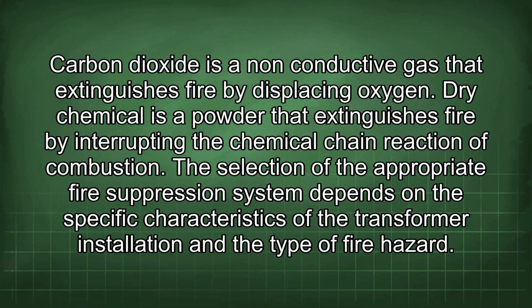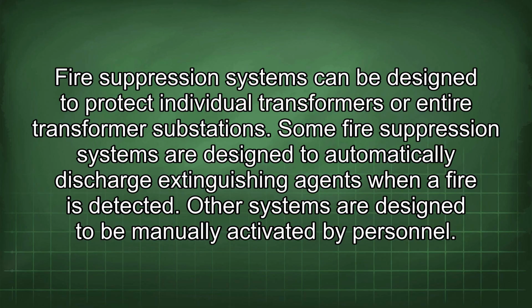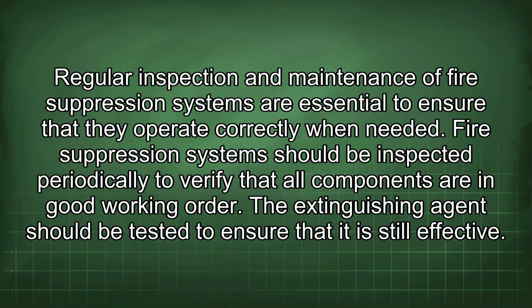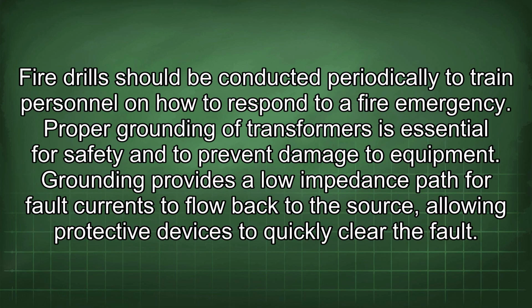The selection of the appropriate fire suppression system depends on the specific characteristics of the transformer installation and the type of fire hazard. Fire suppression systems can be designed to protect individual transformers or entire transformer substations. Some fire suppression systems are designed to automatically discharge extinguishing agents when a fire is detected. Other systems are designed to be manually activated by personnel. Regular inspection and maintenance of fire suppression systems are essential to ensure that they operate correctly when needed. Fire suppression systems should be inspected periodically to verify that all components are in good working order. The extinguishing agent should be tested to ensure that it is still effective. Fire drills should be conducted periodically to train personnel on how to respond to a fire emergency.